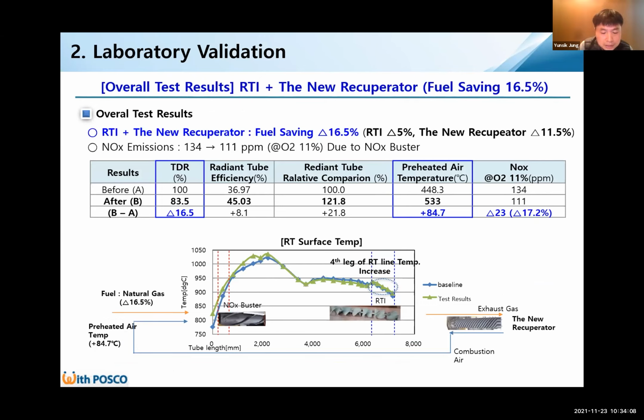I will summarize the overall test result. RTI and the new recuperator bring 16.5% fuel saving, respectively 5% and 11.5%. And its NOx emissions were also reduced by 17.2%, from 134 ppm to 111 ppm. You can find this in the table. All detailed data explain its energy saving effect and NOx reductions. As a result, combustion air temperature is also increased by 84.7 Celsius degrees.